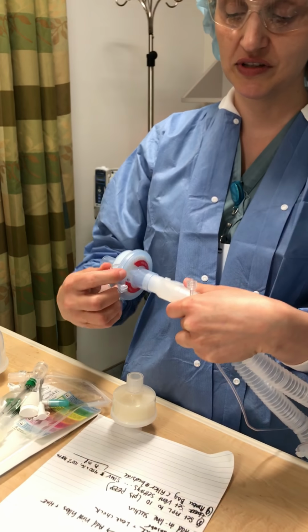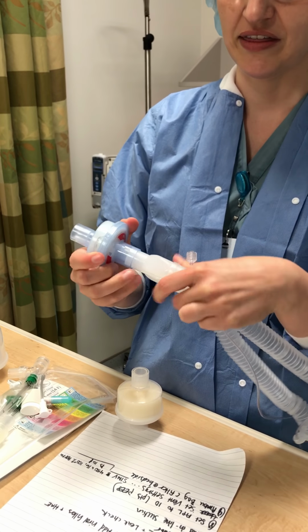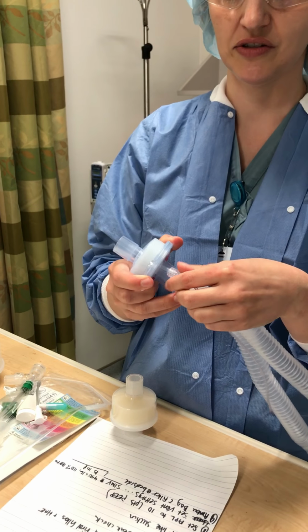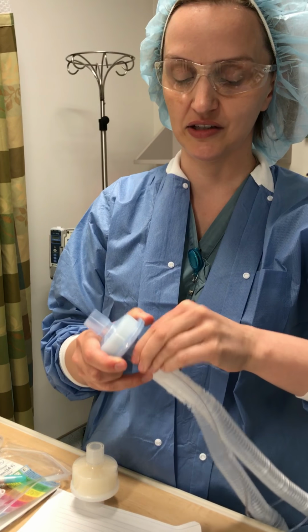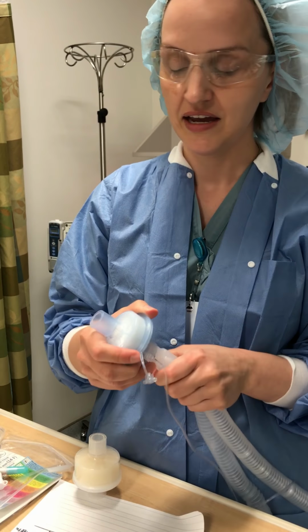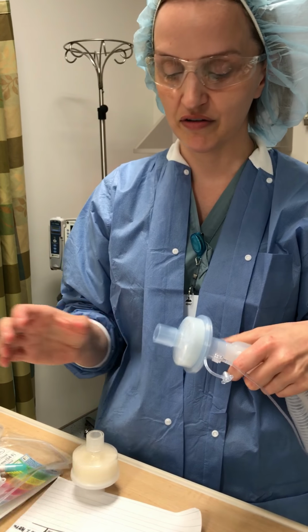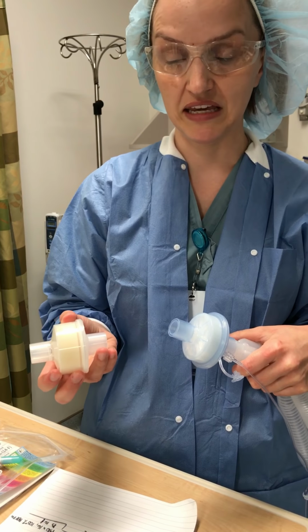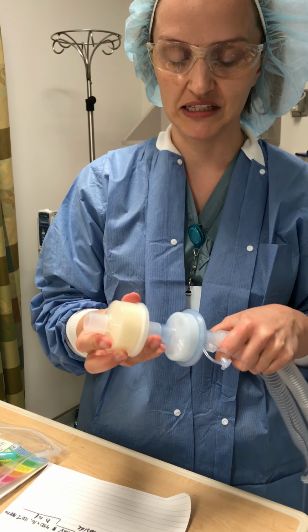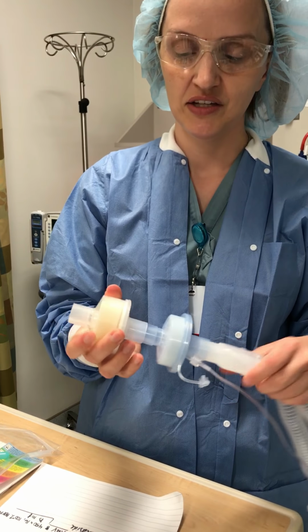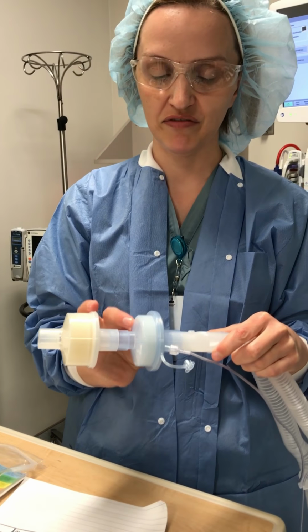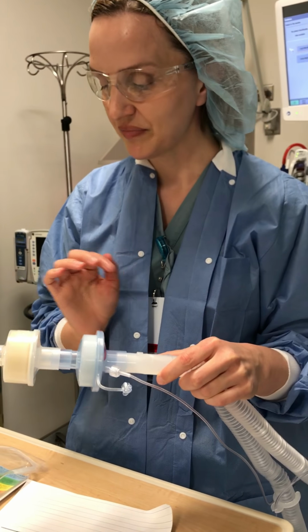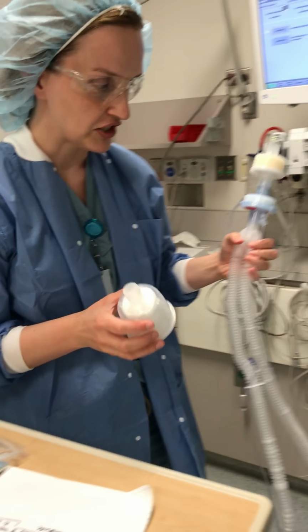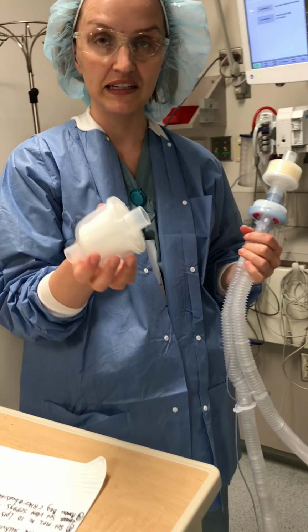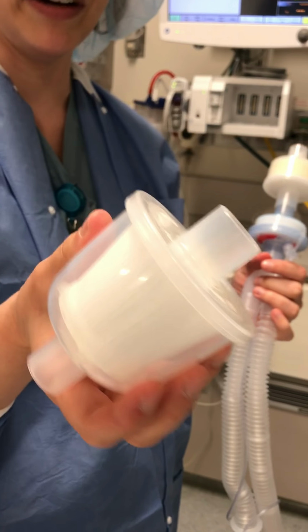And these filters we're choosing to use are called SafeStar, and they actually have a CO2 sampling port here. So you're going to connect your sample line as shown. Okay. Ahead of the viral filter, you're going to place an HME to help the patient maintain humidification of their airways. So this is the patient side, followed by filter, followed by CO2 sampler. And then lastly, before you do your leak check, you're going to want to place a pleated mechanical viral filter at the expiratory limb of the machine.